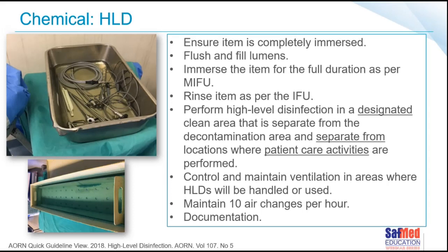As you know, if you look at the images on the left, we can see where the high-level disinfectant hasn't been managed correctly. The lid being left off quite often, and you can see a whole accumulation of fluff and instruments that haven't been properly soaked.